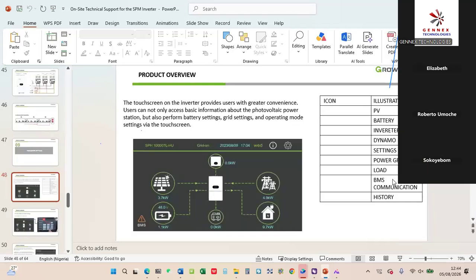Like for the SP, we said you connect it, you choose program 5 and protocol 36, and you either use 51 or 01. But for this, when you get to the screen of the inverter, you turn on the BMS, the communication between the battery and the inverter. That doesn't have a protocol for you to go and choose. But you always make sure you use an RS485 cable for the battery communication process.